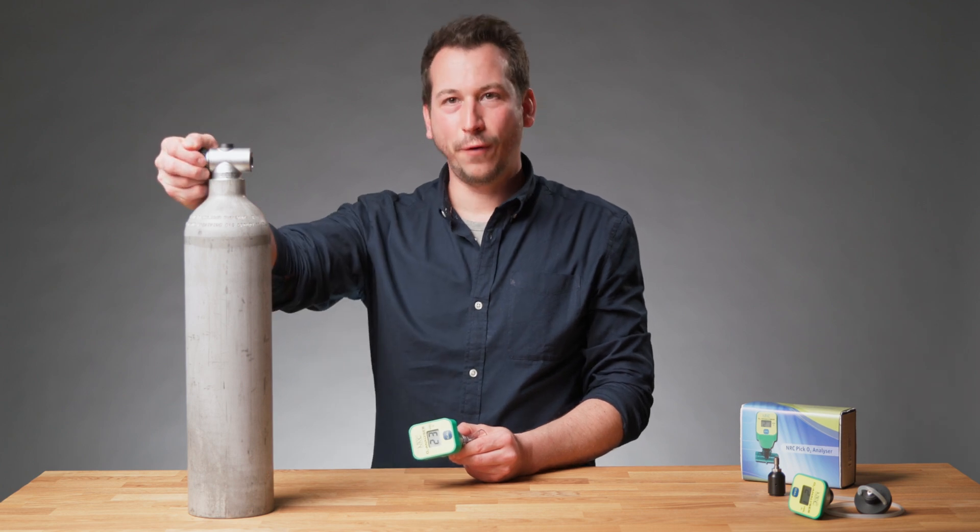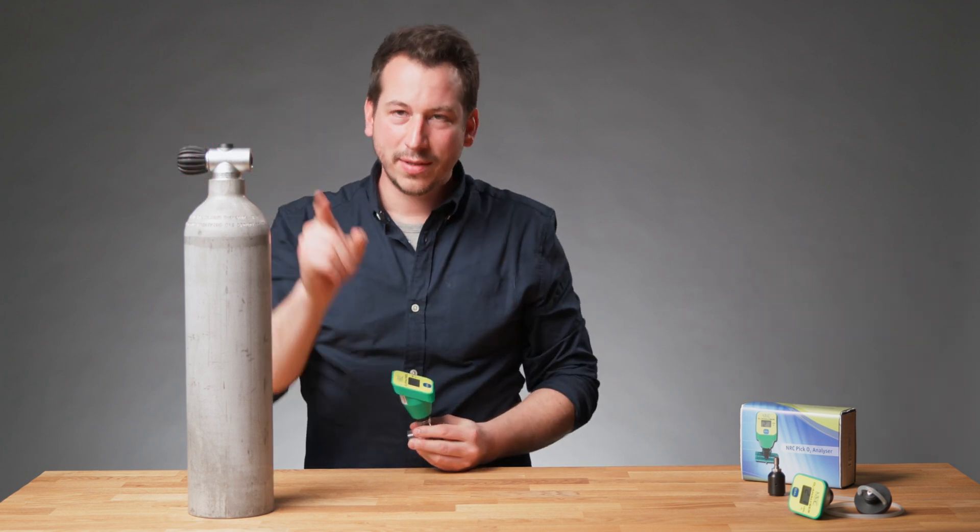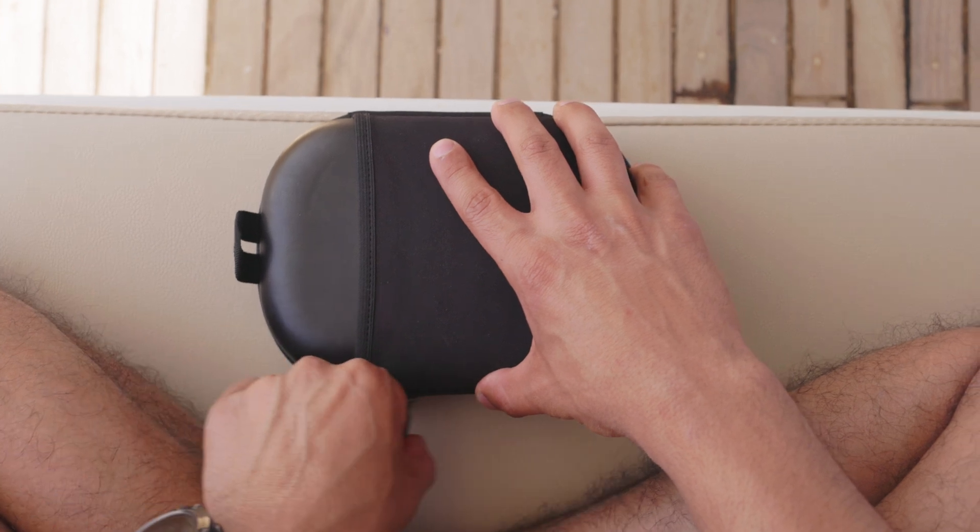Remember, open first the valve gently and after place the analyzer there. If the threads are wet inside, dry them out and keep the analyzer stored in a dry place.